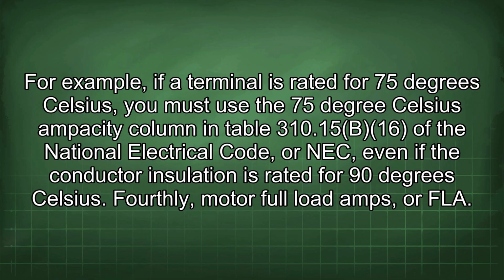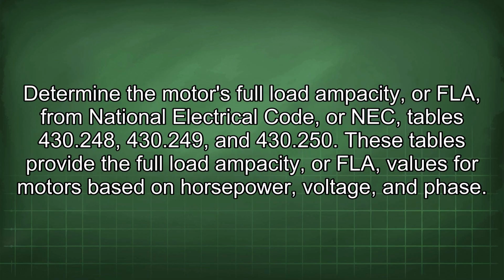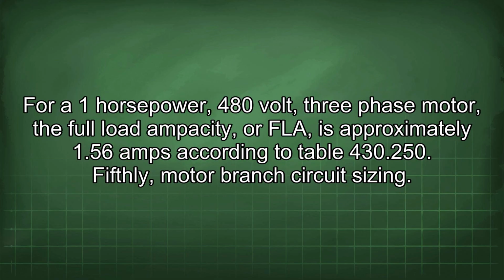Fourthly, motor full load amps, or FLA. Determine the motor's full load ampacity from NEC Tables 430.248, 430.249, and 430.250. These tables provide the full load ampacity values for motors based on horsepower, voltage, and phase. For a 1 horsepower, 480 volt, 3-phase motor, the full load ampacity is approximately 1.56 amps according to Table 430.250.